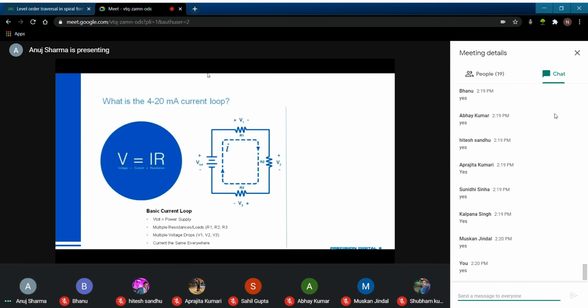R2, and R3. The critical thing to understanding why the current loop is so popular and how to wire it up is that you'll see there's only one I, and that's the dashed looped arrow running through the middle of this circuit. I is the same everywhere. Every element here has a different resistance or impedance, and every element has a different voltage drop or is providing the voltage, but the current is the same anywhere. So if I measure that current between VTOT and V1 in this circuit, it's the same as if I measured it in between V2 and V3. And that's the big strength of this current loop, which we'll discuss in a little bit.